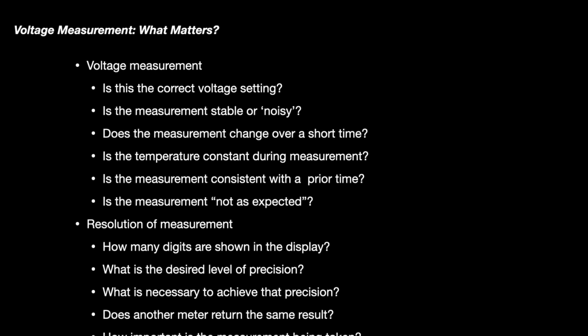Also notice whether the measurement changes over a short period of time. If you measure 5.1 volts and suddenly it's 5.6 volts and then it's 4.8 volts, there's a problem somewhere and you need to find it before you continue with any work with that instrument. If you're doing what you might consider precision measurements, you should take note of whether the temperature varied during the measurement. In other words, if you're working with the meter outside and you go inside, the temperature difference could be 15 or 20 degrees. That's enough to influence the measurement because the meter is still hot from being outside.